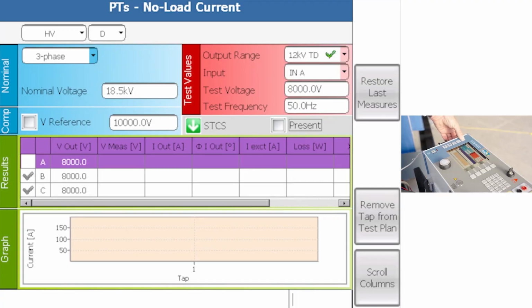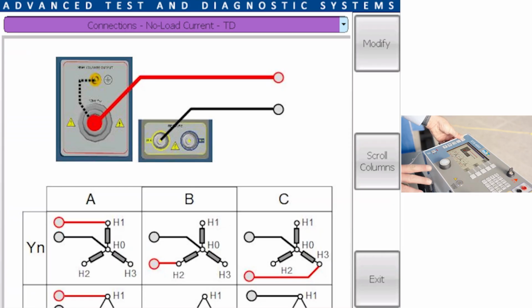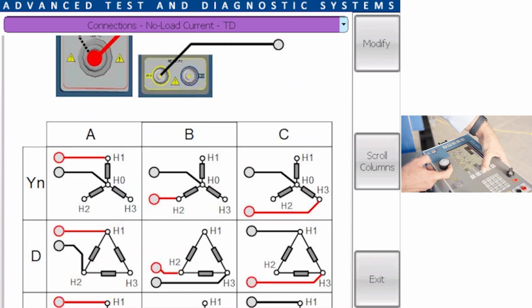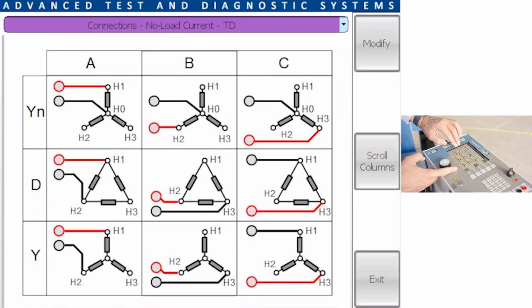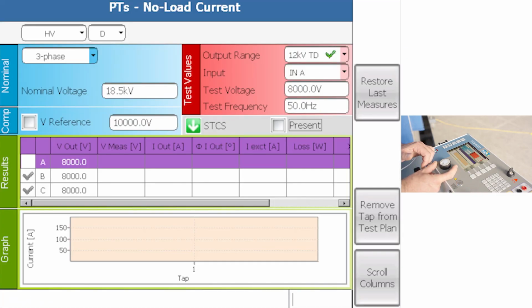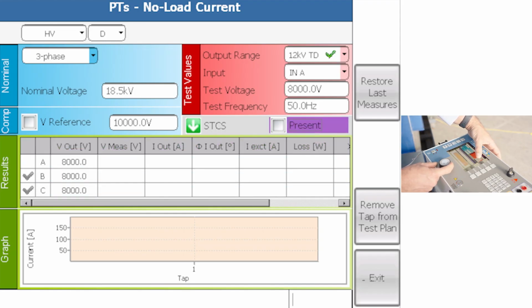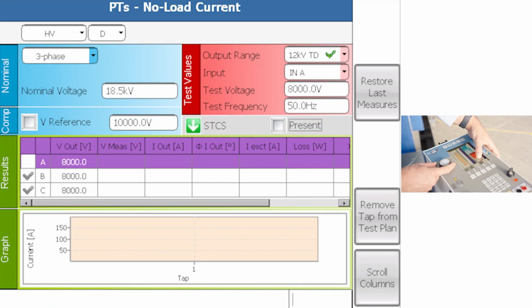Let's see how the connections should be done. So I've decided to use the TD5000 as a source, and in this case, of course, I'm generating on the primary side, so you see how the connections should be done if I'm generating on the primary side. First AB, then BC, and then CA. Of course, you can use just STS as a source, but because I have the TD5000, I decided to generate 8000 volts, 50 Hertz. Now onto phase A. I've marked it and I press start.